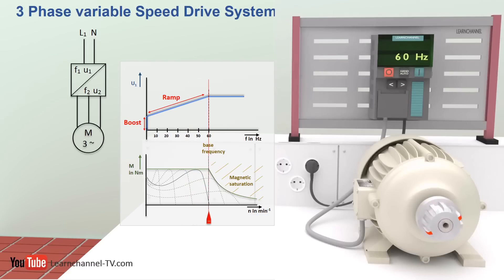The parameter called Ramp describes the voltage-frequency ratio. The other parameter, Boost, also known as Torque Compensation, is to compensate the torque decrease at low speed because of the stator winding resistance of the electric motor and the starting torque caused by friction.